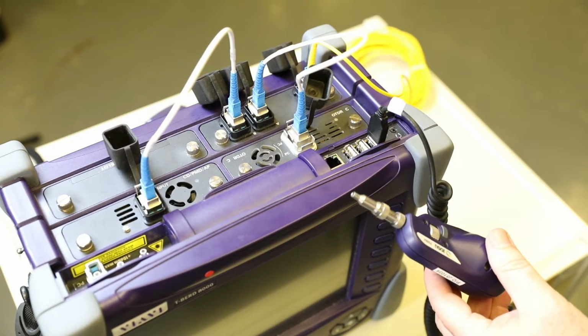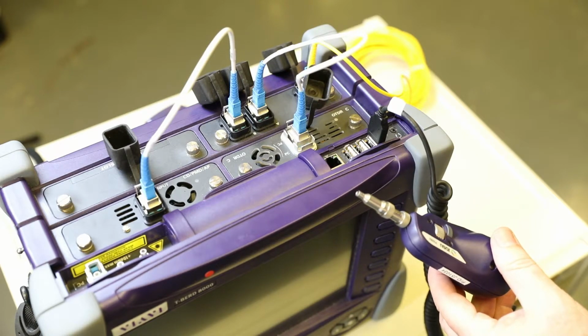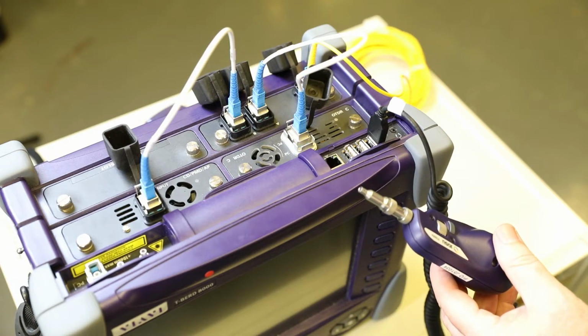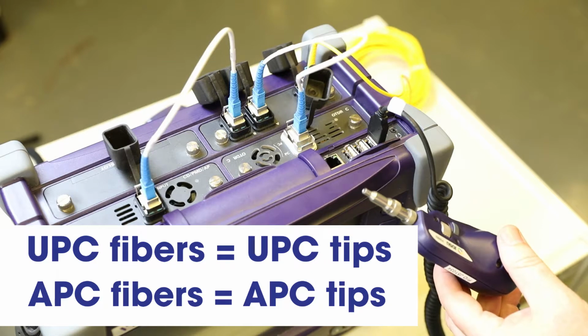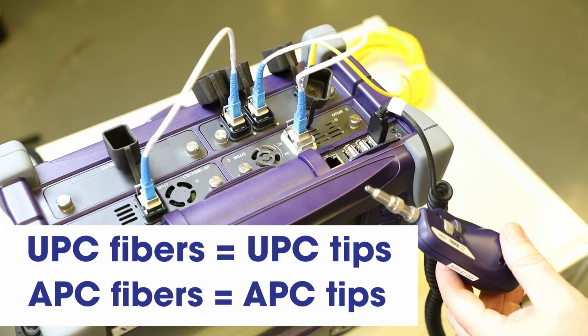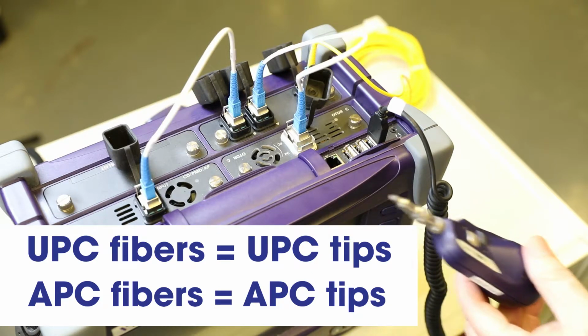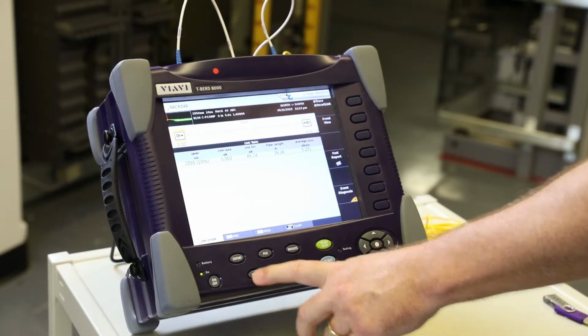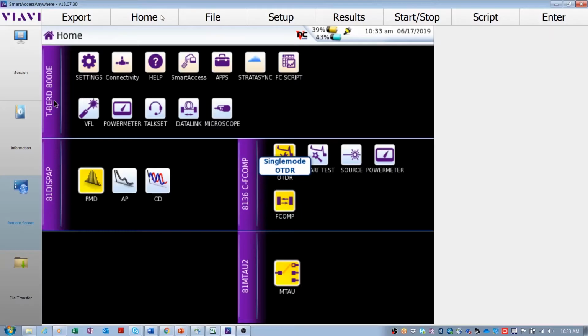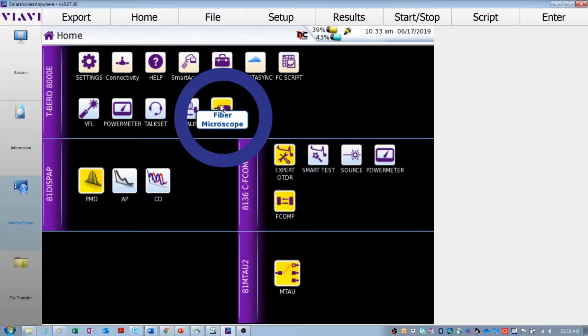Attach the required tip to the P5000i. Note UPC fibers need UPC tips and APC fibers need APC tips. Press the home hard key once the T-BERD is on. Activate the P5000i by touching the microscope icon twice with finger or stylus. The P5000i is activated once the icon turns yellow.